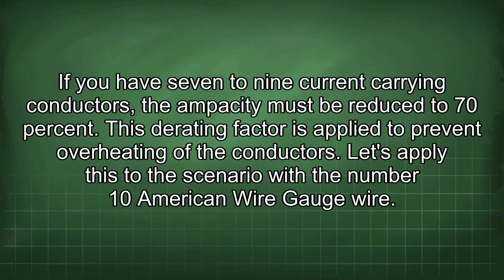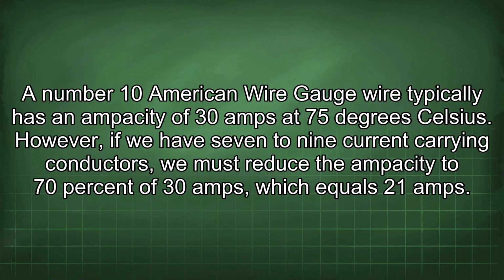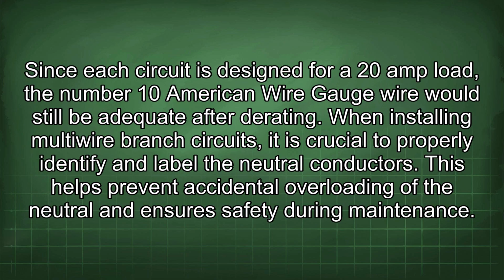Let's apply this to the scenario with the number 10 American wire gauge wire. A number 10 American wire gauge wire typically has an ampacity of 30 amps at 75 degrees Celsius. However, if we have 7 to 9 current-carrying conductors, we must reduce the ampacity to 70% of 30 amps, which equals 21 amps. Since each circuit is designed for a 20 amp load, the number 10 American wire gauge wire would still be adequate after derating.